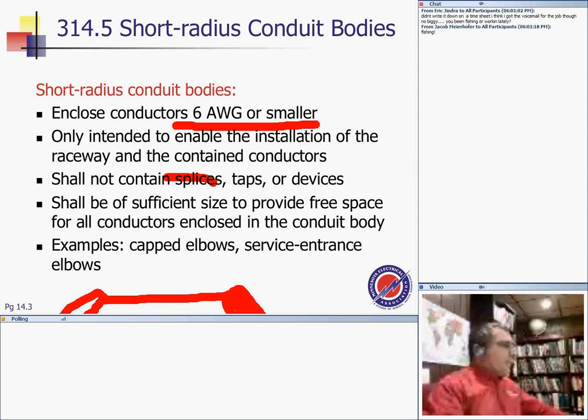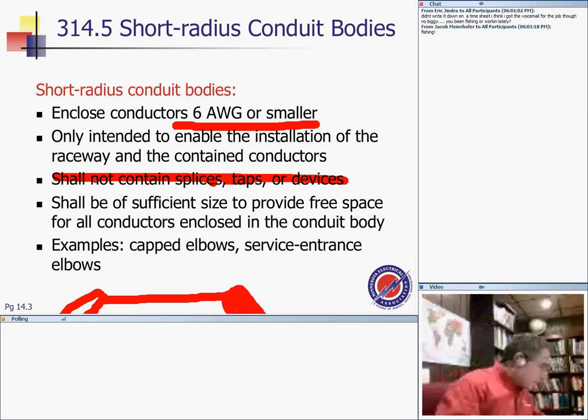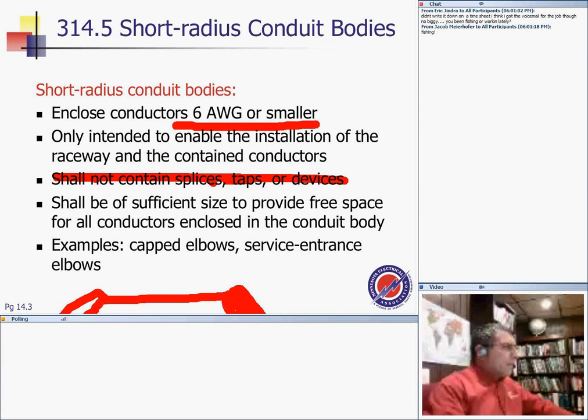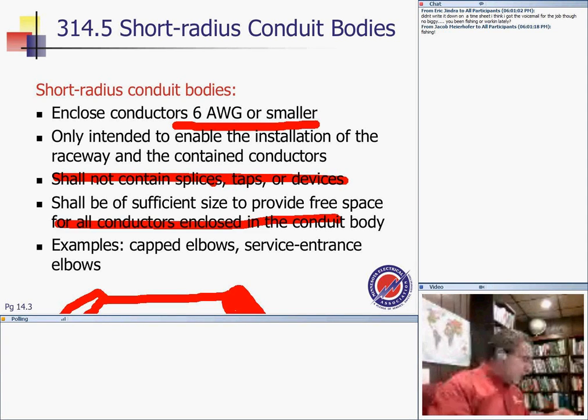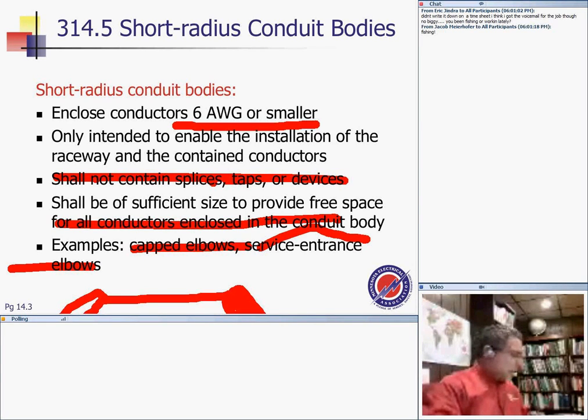They shall not contain splices or taps or devices unless they are listed. There could be places where you can put splices and devices, as a matter of fact. They shall be of sufficient size to provide free space for all conductors enclosed in the conduit body. So you have room for all the conductors that go through it. Capped elbows, service-entrance elbows, and all these are good examples of conduit bodies, for ease of installation of conductors number 6 or smaller. Number 6 or smaller.